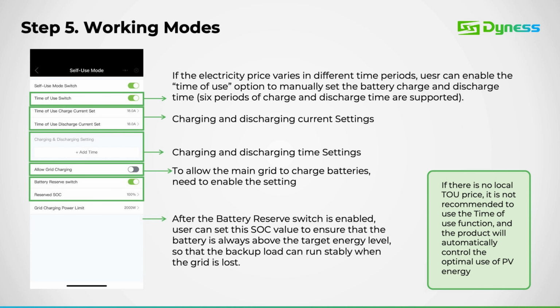Here's an overview of the self-use mode setting. On this page, you'll find several options available within this working mode. You can enable time of use and set the charge and discharge times for your system. Additionally, we offer the battery reserve option, which is particularly useful for load shedding, as it ensures the set battery SOC percentage remains available when needed. Finally, there's the grid charge option for when it's required. This concludes the initial commissioning of the inverter.